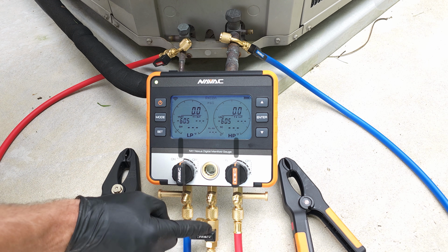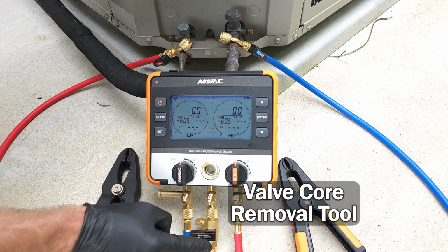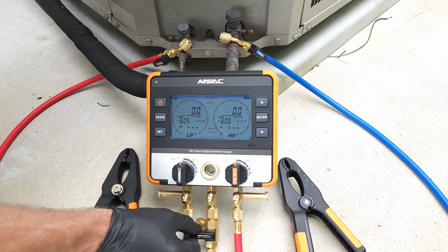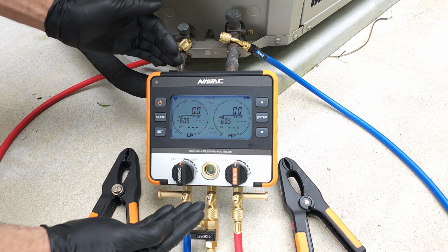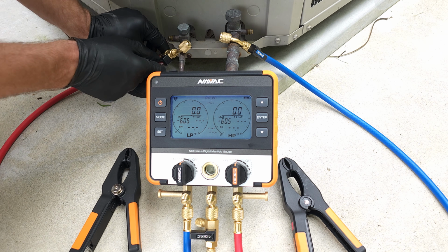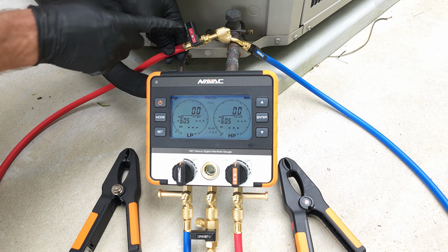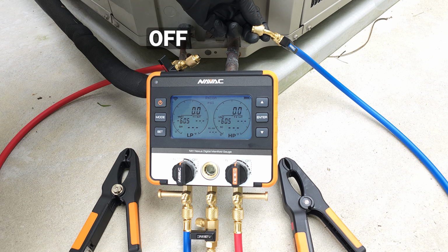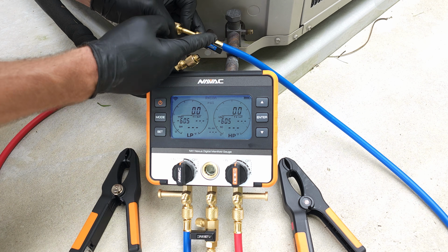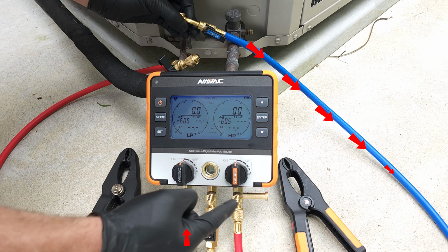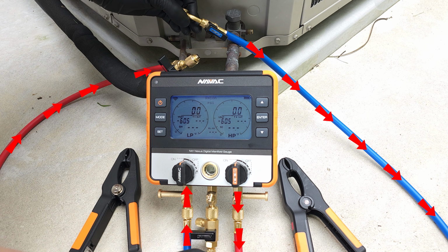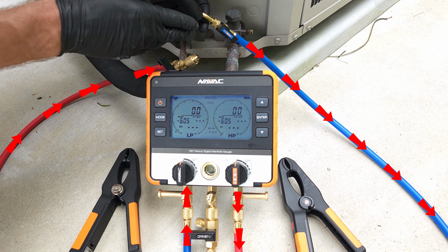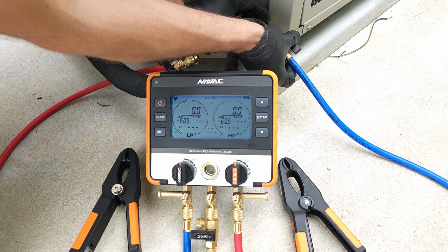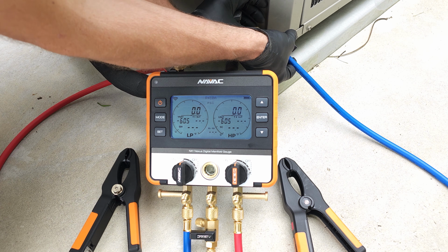And we have a valve core removal tool here instead of a yellow service hose. And we've done that just to turn this valve to the off position. During the air purging process, we are going to turn this red hose to the off position and we're going to connect it in. That's going to allow any air from here to flow through the manifold, out through the red hose and over to here. That's how we're going to get rid of the air in the hoses so we don't accidentally contaminate the system.